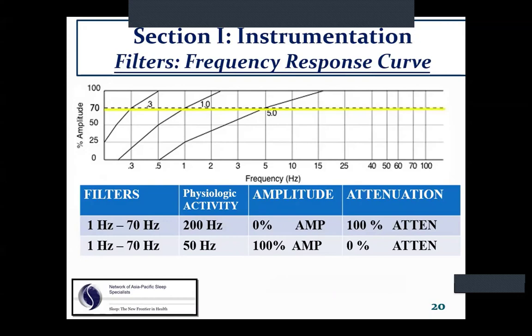So it's important that you know your target frequency, which is really different between respiratory channels, chin channels, EKG, EEG, to ensure that you include a filter bandwidth or bandpass that covers the target frequencies. Now you would think that if my filters are set from 1 to 70 hertz, 100% of a 1 hertz waveform would be seen in amplitude, and 100% of 70 hertz activity would be seen in amplitude. But it's not true. A unique phenomenon happens when frequency equals filter setting.